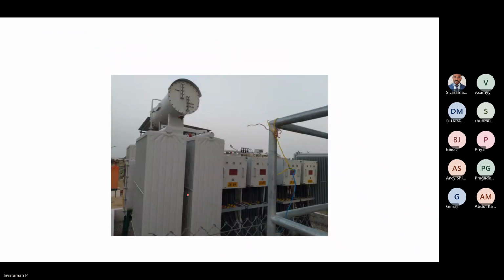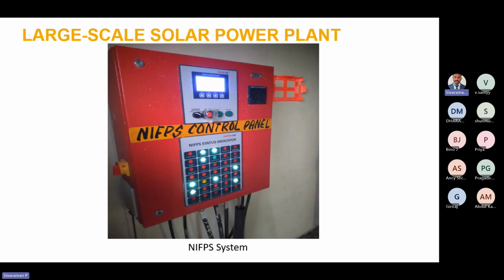What you are seeing is the 4 LV windings: winding 1, 2, 3, 4. The inverter output is connected to this inverter duty transformer through this cable. In this photo, what you are seeing right here is a cable, and it is used to connect this inverter duty transformer to the inverter. On the opposite side, the medium voltage terminal will be there, that is 33 kV. From that terminal, it will go to the switchgear. This is the NIFPS system.